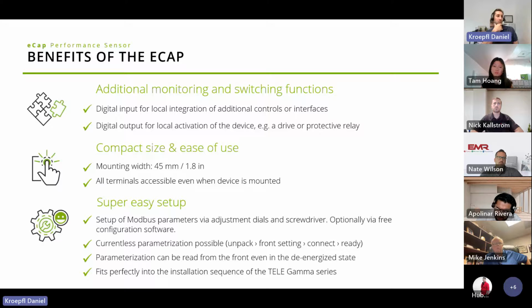One thing we're proud of is that you really don't need to power up the device to set any parameters in terms of Modbus. So that's the ease of use. Optionally, we also offer a free configuration software if they really want to get in depth when it comes to, for example, arranging the CT ratios and whatnot.